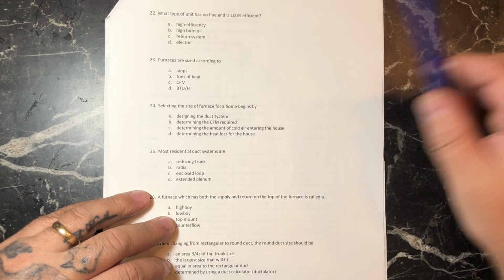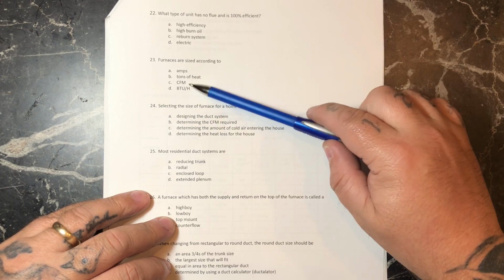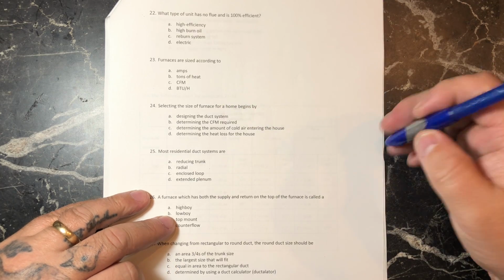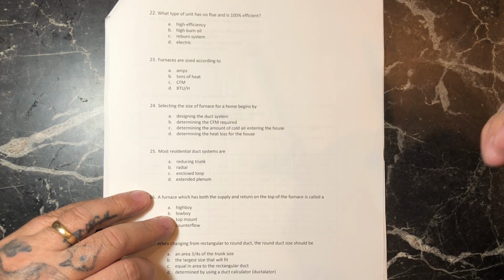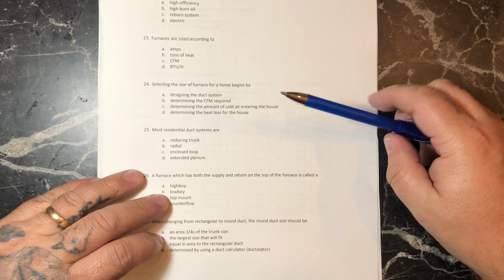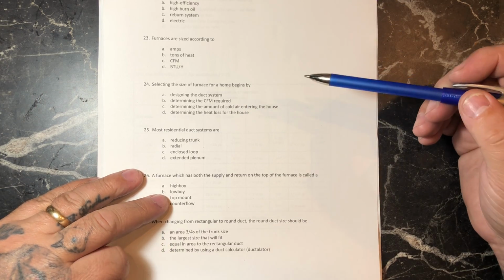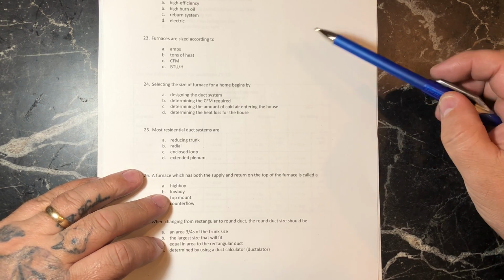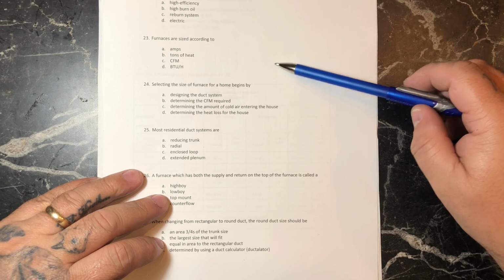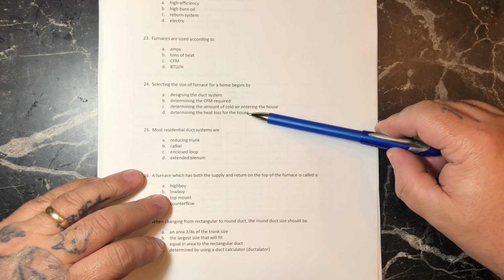And then depending on how many BTUs or tons of heat or cooling, that's going to determine how many CFM there are. So that one's D. Selecting the size of a furnace for a home begins by, I've already said this a few times, determining the heat loss for the house.